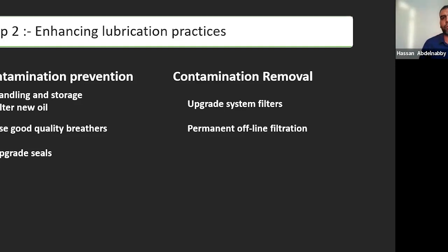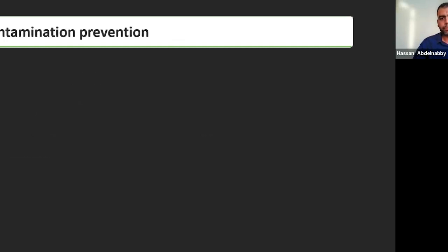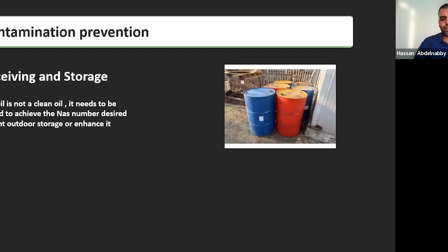When you enter a factory and don't know where to start, check the lubrication plan, check the OEM recommendations, and verify whether the plan is actually being followed on site. You need to fight contamination on two fronts — the prevention side and the removal side. For prevention, starting with receiving and storage: new oil is not clean oil; you need to filter it to reach the required cleanliness level.